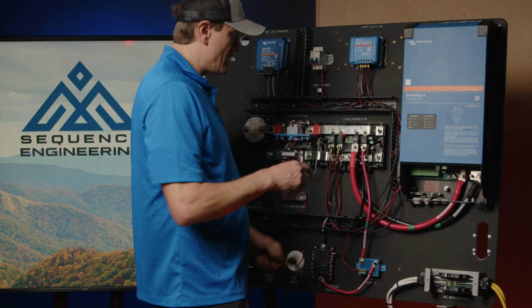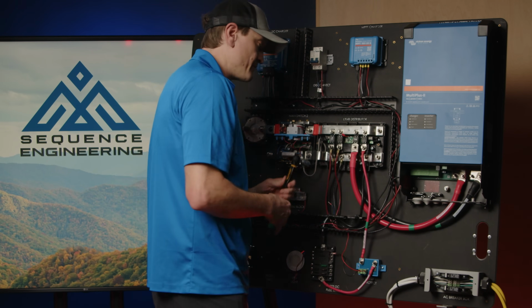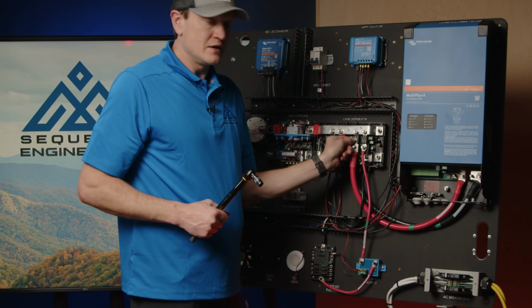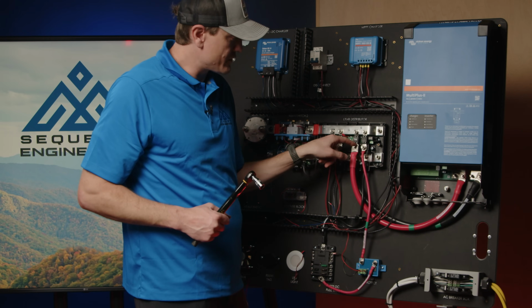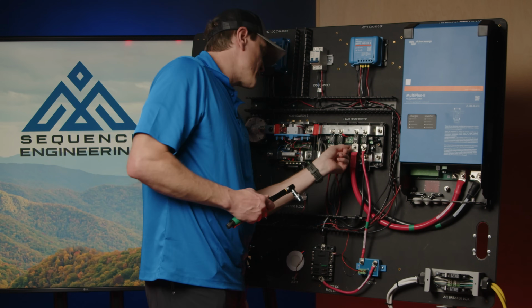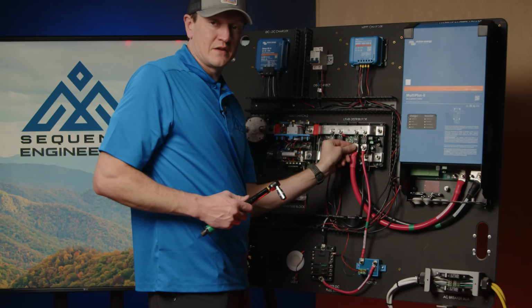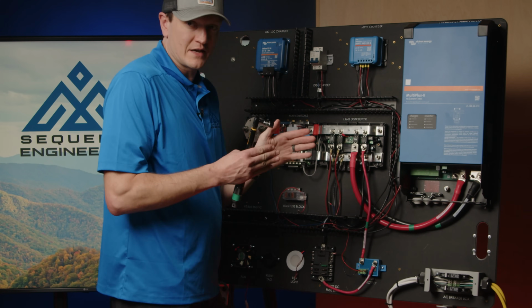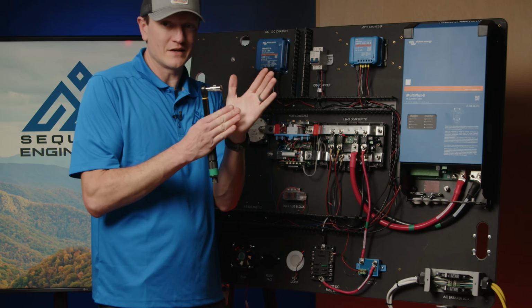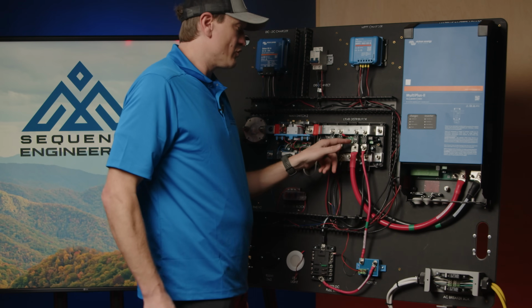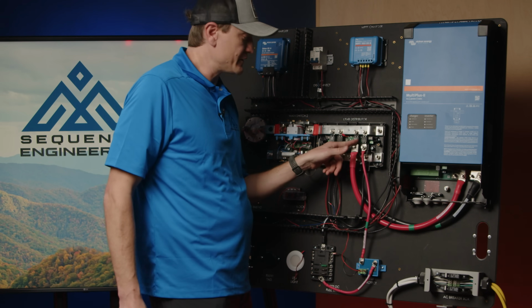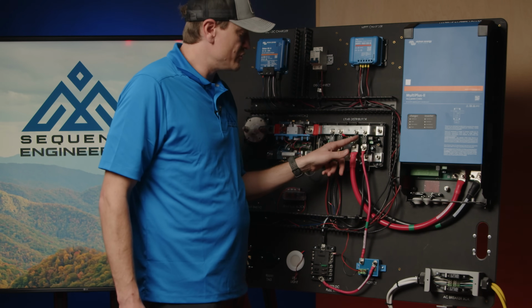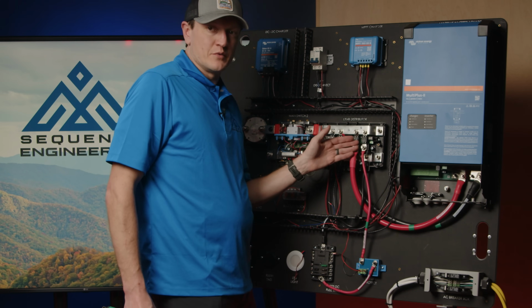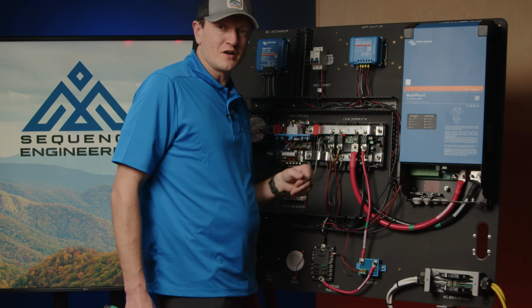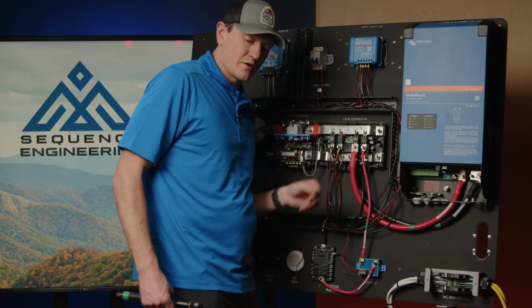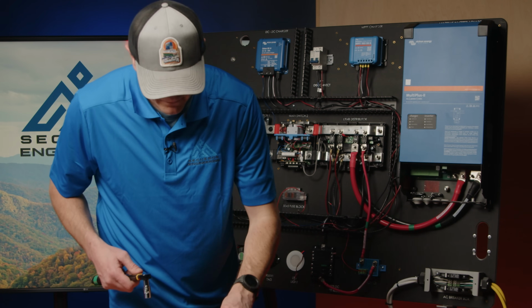Now we're going to move over to this connection and connect it to our fuse. One thing to note is there's a bit of interference on the mega fuse and where the lug comes together. What's going to happen is this lug and this fuse will come together, and as you tighten them, the fuse will deform such that it makes contact with the lug. Newer versions of the mega fuse, which Victron now sells, have a recess that allows you to use these mega fuses with these larger lugs. But in this particular example, it probably won't look very awesome - we do get a lot of questions about it, but it will be functional for this demonstration.